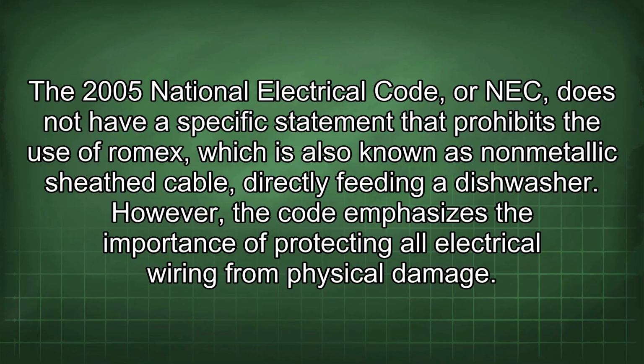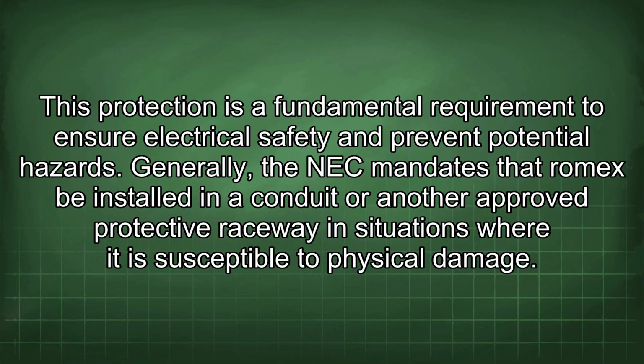The 2005 National Electrical Code, or NEC, does not have a specific statement that prohibits the use of Romex, which is also known as non-metallic sheath cable, directly feeding a dishwasher. However, the code emphasizes the importance of protecting all electrical wiring from physical damage. This protection is a fundamental requirement to ensure electrical safety and prevent potential hazards.